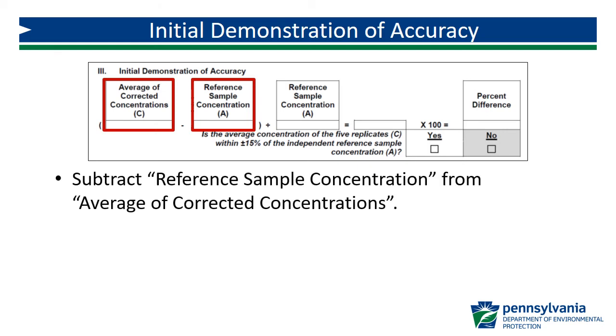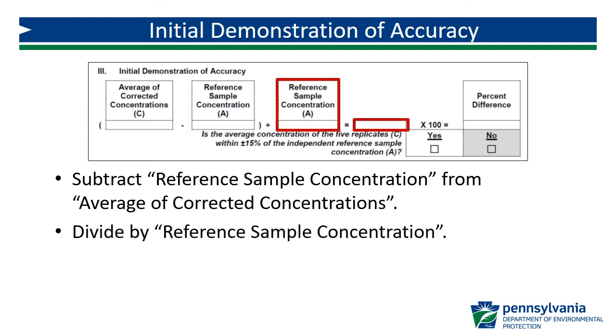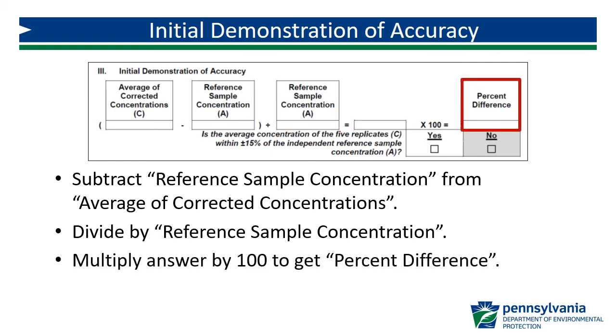Transfer the values for average of corrected concentrations and reference sample concentration into their respective fields. C is the average of corrected concentrations and A is the reference sample concentration. Subtract the reference sample concentration, A, from the average of corrected concentrations, C. Divide this result by the reference sample concentration, A, and record the value. Multiply this result by 100 to determine the percent difference.